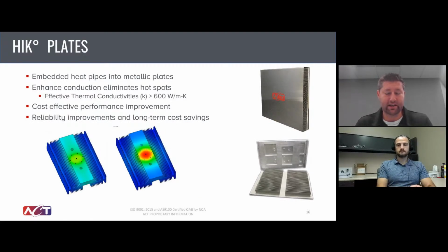Now we'll look at that exact example that I just mentioned. In many cases in the power electronics world, the goal is to eliminate hotspots. One of the areas that we've explored a lot is embedding heat pipes into metallic plates, in most cases aluminum, because it's fairly cost effective and already has some good thermal properties. By embedding heat pipes into aluminum plates, you can increase the thermal conductivity of those plates by a couple of factors. Aluminum is typically somewhere between 150 and 200 watts per meter K. By implementing heat pipes, you can easily achieve 600 watts per meter K, and in certain cases, if you have long distance heat transfer, you could achieve over 1,000 watts per meter K.